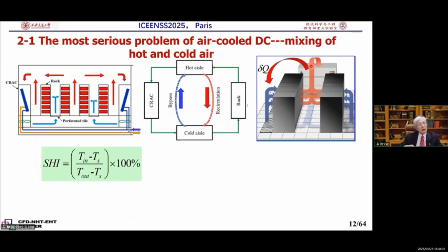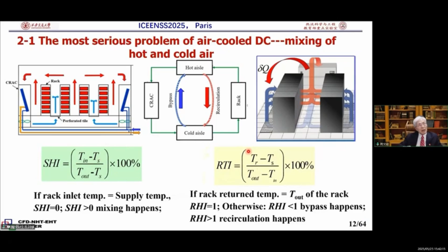Now, first we talk about the front of the rack. If the inlet temperature of the rack is equal to the supply temperature, then the numerator equals 0. So SHI equals 0. That means if there is no mixing, SHI should be equal to 0. Okay? At the back of the rack, it's the hot temperature. If the return temperature equals the outlet temperature of the rack, then RHI equals 1. So if there is no mixing at the back of the rack, RHI should equal 1. If less than 1 or larger than 1, then some mixing of hot and cold gas happens.